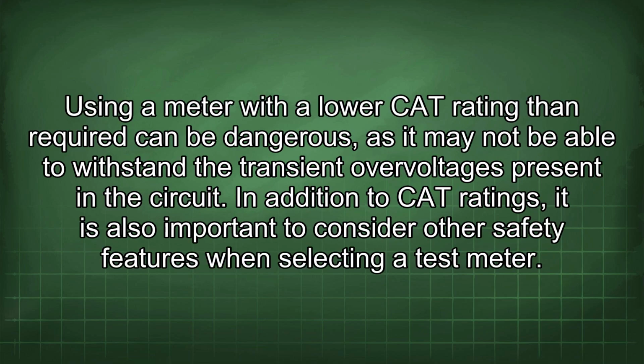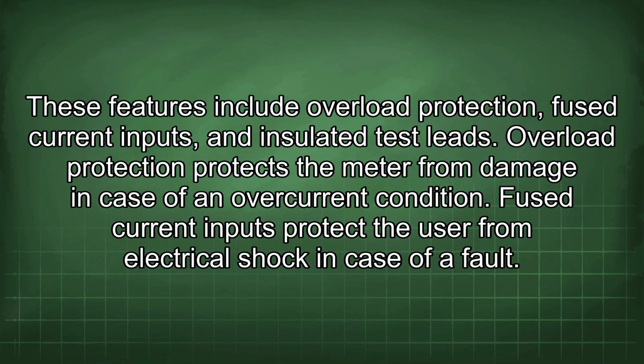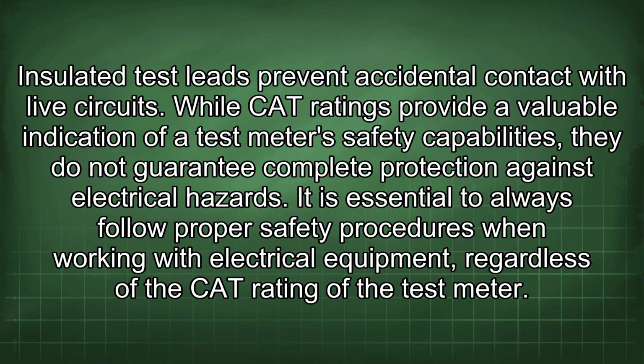Using a meter with a lower CAT rating than required can be dangerous, as it may not be able to withstand the transient overvoltages present in the circuit. In addition to CAT ratings, it is also important to consider other safety features when selecting a test meter. These features include overload protection, fused current inputs, and insulated test leads. Overload protection protects the meter from damage in case of an overcurrent condition. Fuse current inputs protect the user from electrical shock in case of a fault. Insulated test leads prevent accidental contact with live circuits.